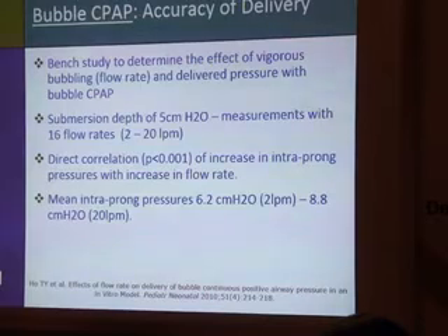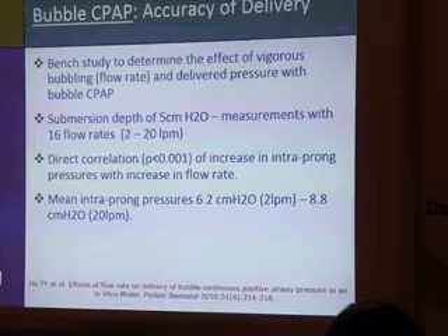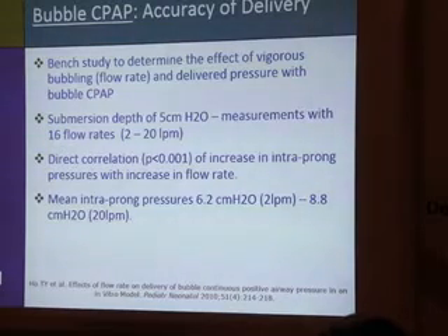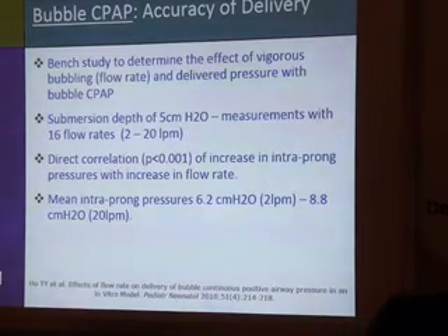They saw a direct correlation with an increase in pressure in the prongs with an increase in flow. So as you change your flow rate, you're going to get more CPAP, even though you haven't changed your submersion depth past 5 centimeters of water pressure. So it's an interesting development. And on average, their intra-prong pressure was 6.2 at 2 liters per minute up to 8.8 at 20 liters per minute. So even when they started at 2 liters per minute with a submersion depth of 5, they didn't get 5, they were getting 6.2.